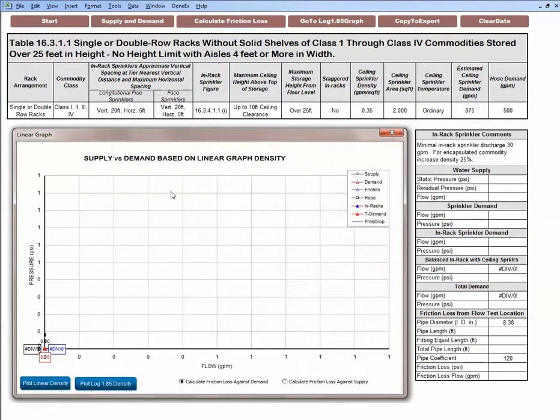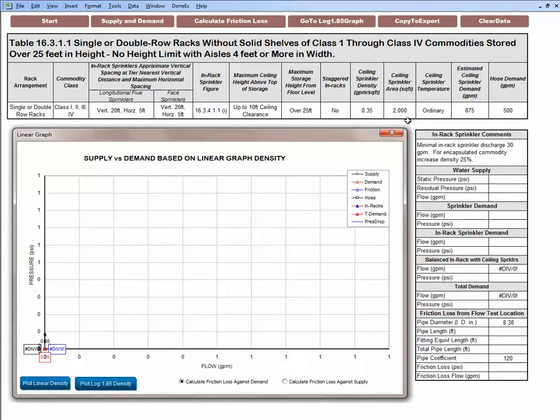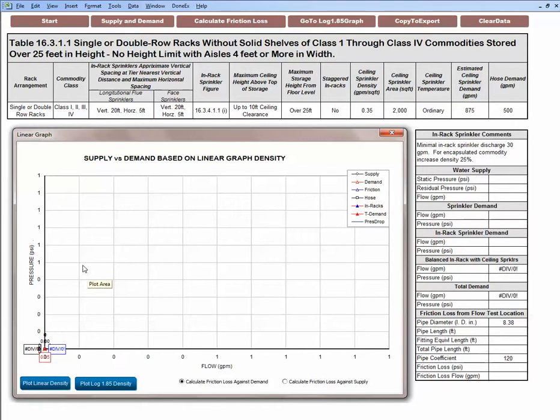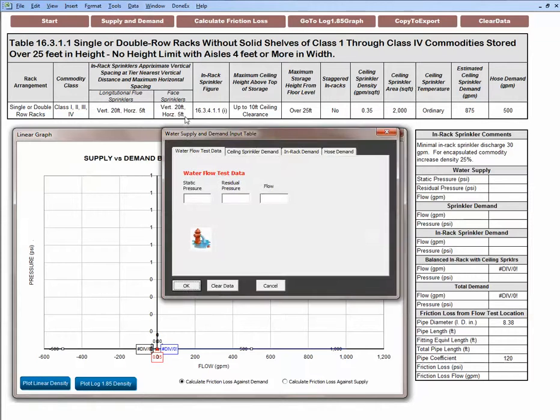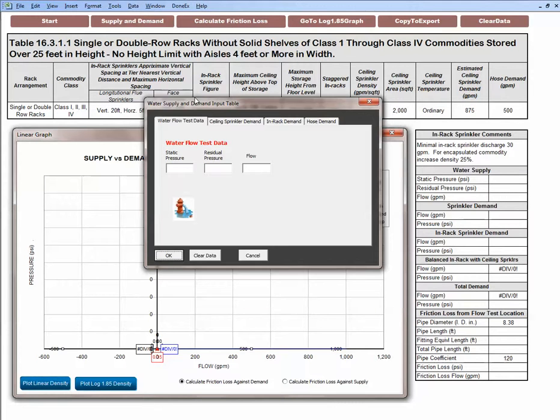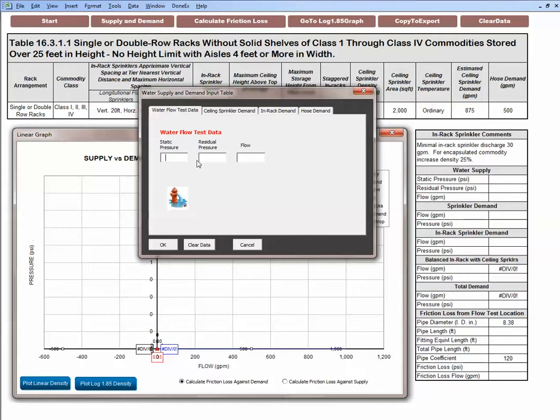I'm going to click next, information is already populated and now we need to enter water supply. I'm going to enter the water supply given to me at the site that I pulled from sprinkler diagrams and hydraulic calculations. I click supply and demand button and this window opens. Now I enter the water supply that was given to me from city water pressure and a 1250 gpm booster pump. The static pressure is 170, I entered 170.